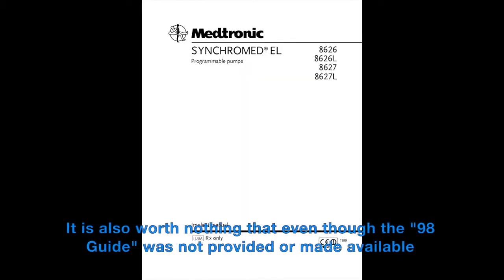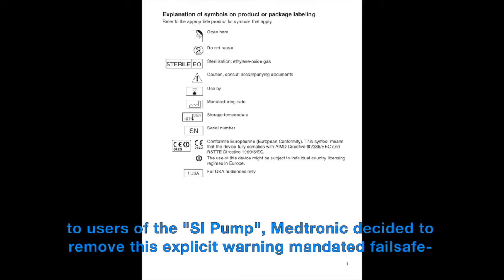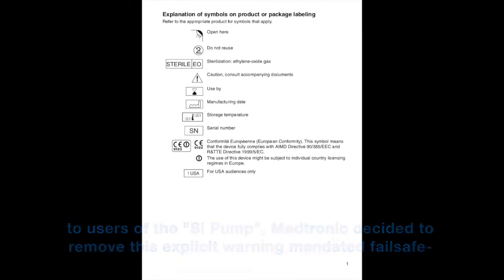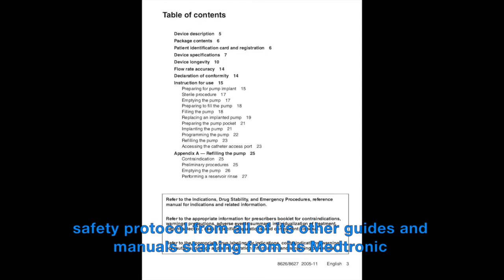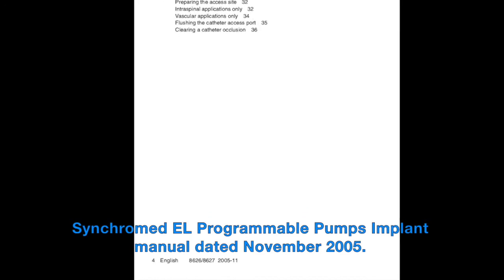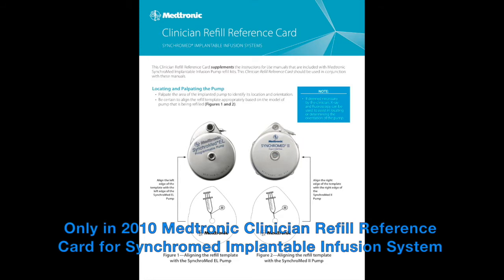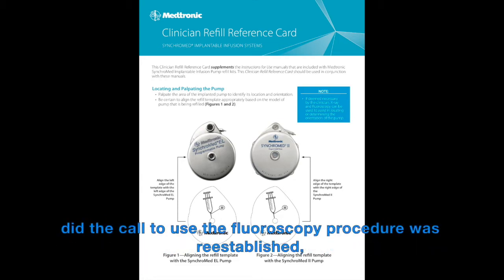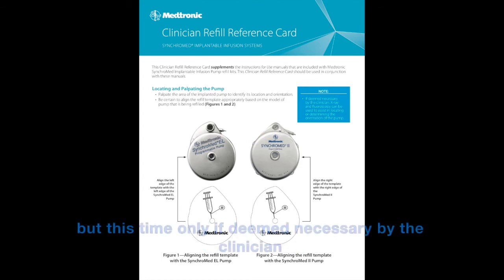It is also worth noting that even though the 98 guide was not provided or made available to users of the SI pumps, Medtronic decided to remove this explicit warning, a mandated fail-safe safety protocol, from all of its other guides and manuals starting from its Medtronic SynchroMed EL Programmable Pumps Implant Manual dated November 2005. Only in 2010, with the Medtronic Clinician Refill Reference Card for SynchroMed Implantable Infusion Systems, was the call to use the fluoroscopy procedure re-established, but this time only if deemed necessary by the clinician.